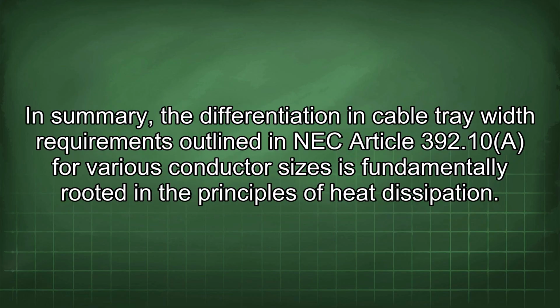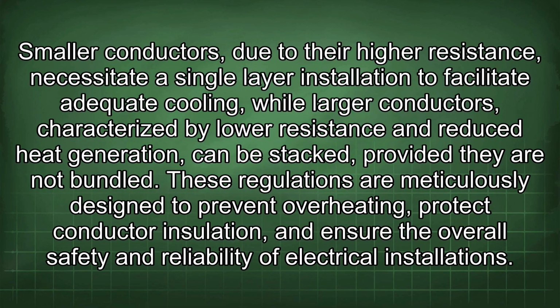In summary, the differentiation in cable tray width requirements outlined in NEC Article 392.10 for various conductor sizes is fundamentally rooted in the principles of heat dissipation. Smaller conductors, due to their higher resistance, necessitate a single-layer installation to facilitate adequate cooling, while larger conductors, characterized by low resistance and reduced heat generation, can be stacked, provided they are not bundled.